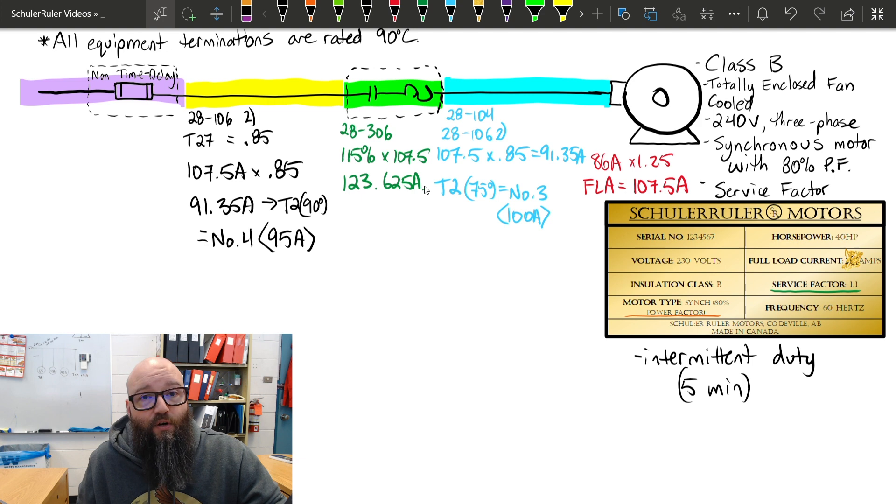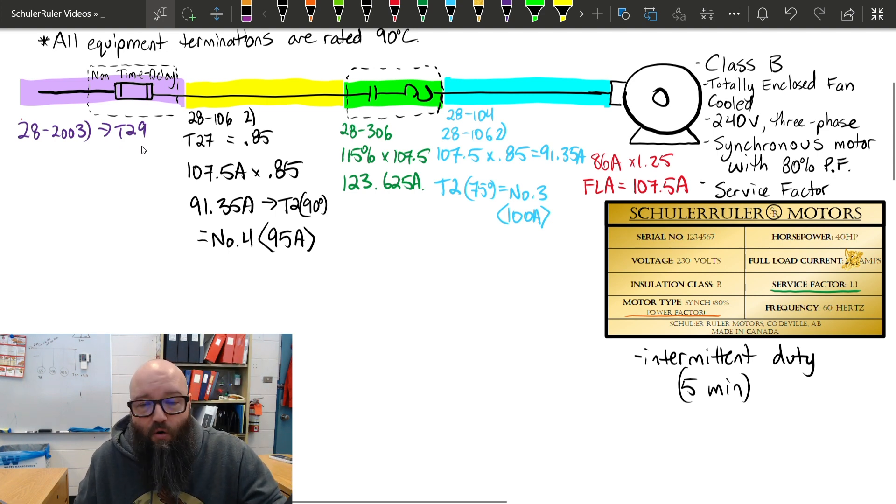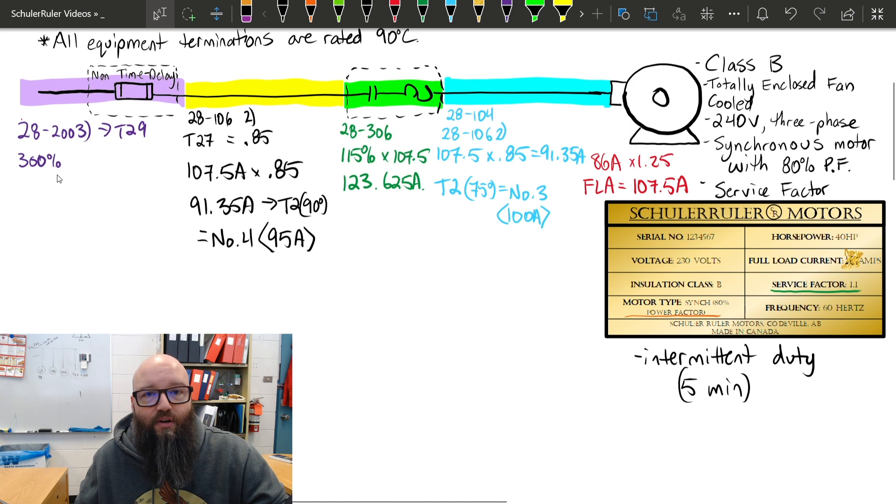Our overcurrent device. Again, nothing changes as far as the calculation. We're still going to refer to that 28200 subrule 3, which tells me go to table 29. You'll notice for synchronous motors it's under the same row as squirrel cage induction motors, but since we're using a non-time delay fuse in this example, we actually get a multiplier of 300%. It tells me in 28200 I cannot exceed that table 29 value multiplied by my FLA.